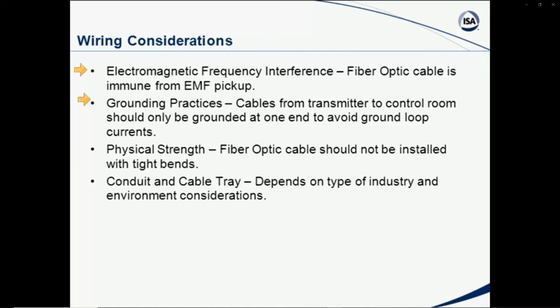For instance, in a conventional electronic analog, you don't want to ground the transmitter cable at both ends. You'd only want it grounded at one end. If you grounded at both ends, you could set up ground loop circulating current. So you don't want to do that. There could be questions involved about physically how to install some of the cable that you might be running in an industrial plant or any type of a power facility or whatever.